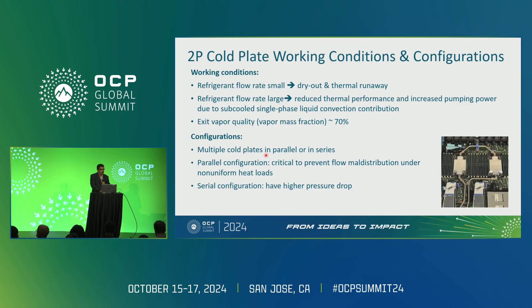For working conditions, the maximum vapor quality must be kept at 70% per loop, whether serial or parallel. We have a demonstration with one loop at 1.1 kW and four in series making 4 kW — the same principle applies and works exactly the same, with no temperature change from one loop to another.